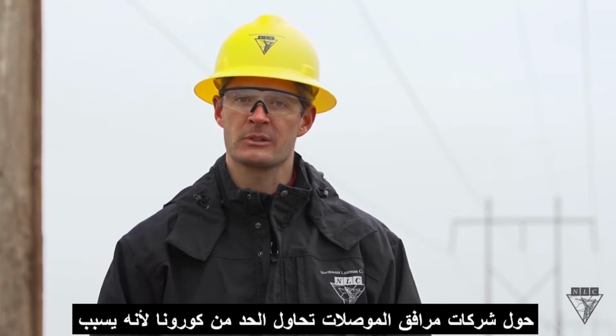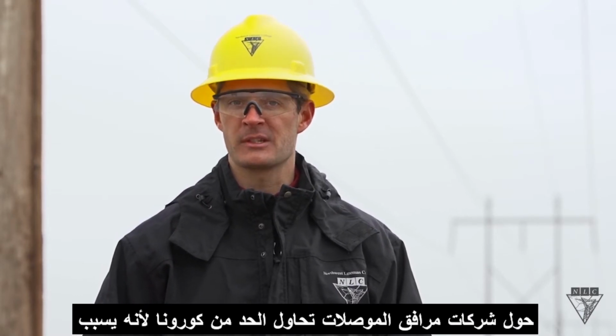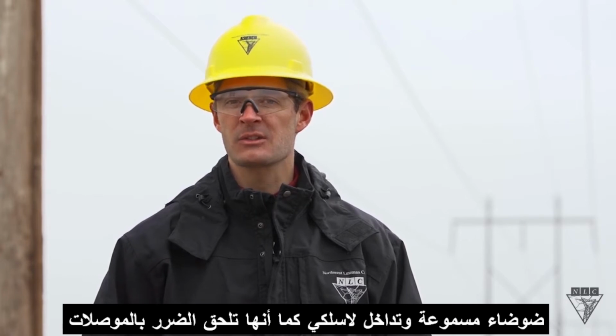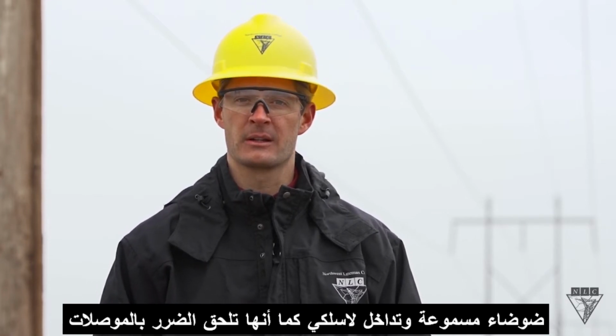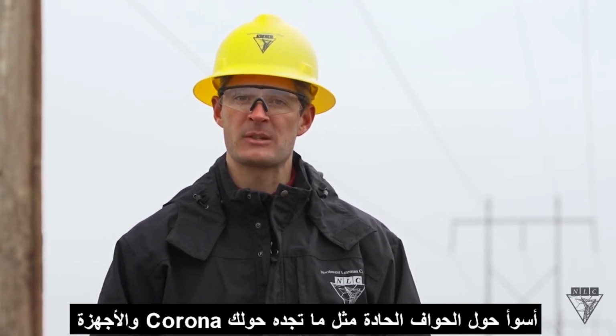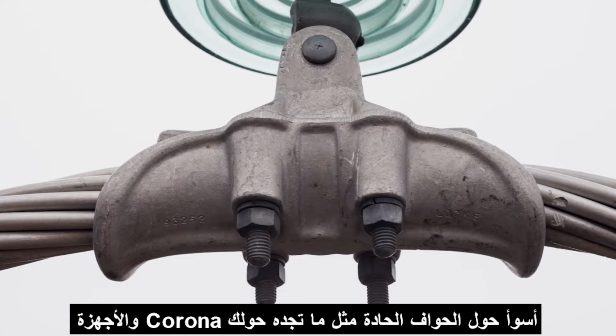Utility companies try to reduce corona because it causes audible noises and radio interference, and it's also damaging to the conductors and hardware. Corona is worse around sharp edges, like what you find around the end of suspension and dead-end hardware, and where there's nicks and scrapes.